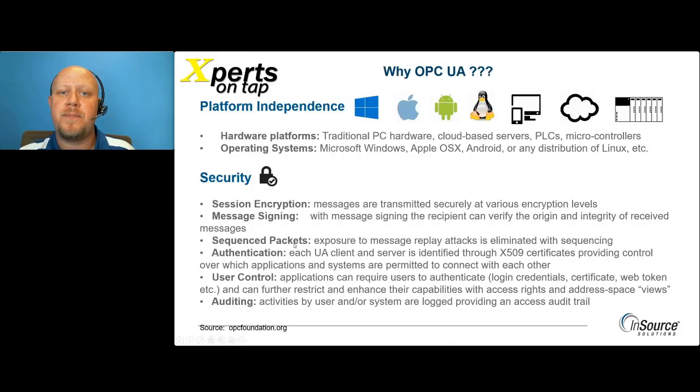Let's get started. One of the big advantages to utilizing OPC UA is its platform independence. You can speak across multiple operating systems, pieces of software, or hardware seamlessly. Another big advantage of OPC UA is its security. OPC UA utilizes X509 certificates, which means that you can be sure you're talking securely to other platforms or PCs. This is much cleaner than the OPC DA approach, which utilizes DCOM and can get very messy.